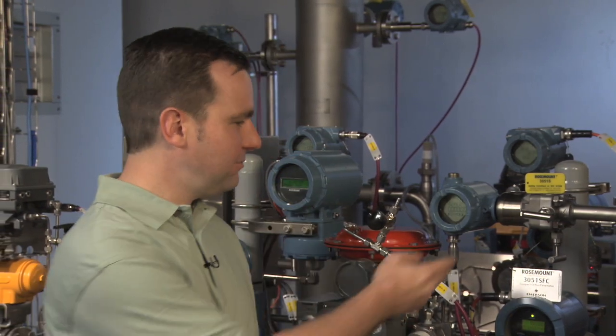We're with Emerson Process Management, and we're going to demonstrate the power of our predictive intelligence from the Smart SIS technology that's provided by the Rosemount 3051S pressure transmitter. In this video, we're going to use DeltaV SIS to show how the 3051S can detect a plugged impulse line.